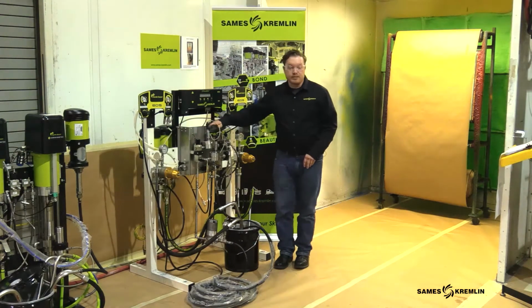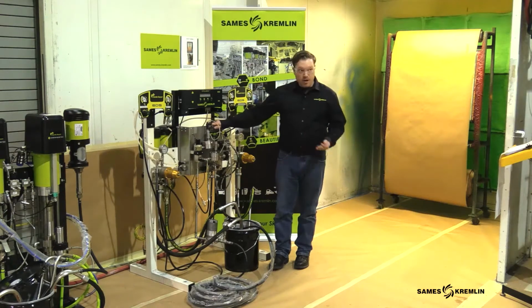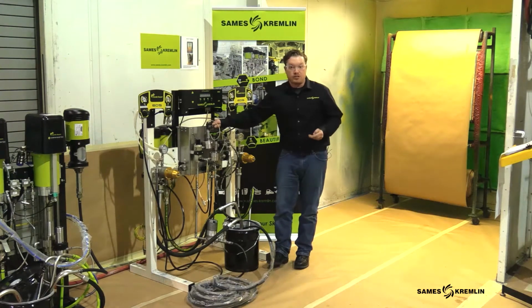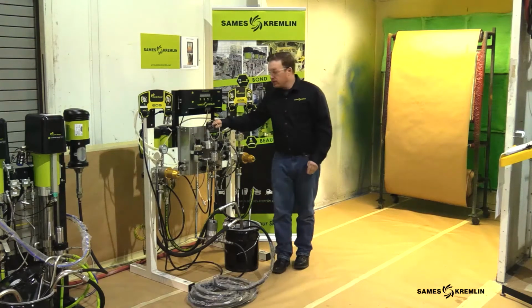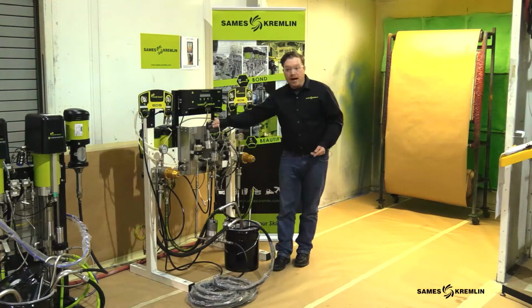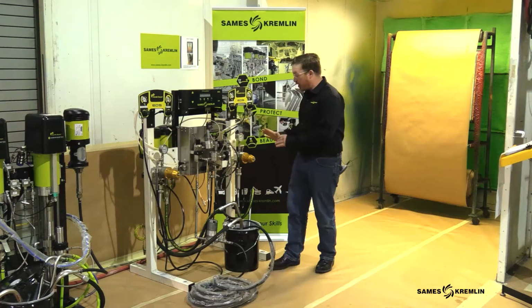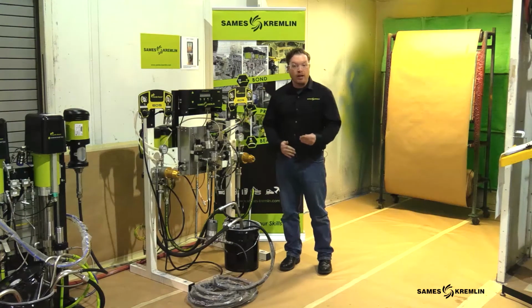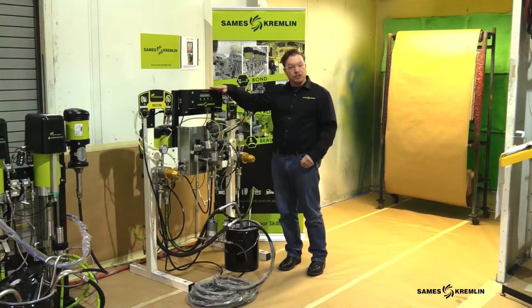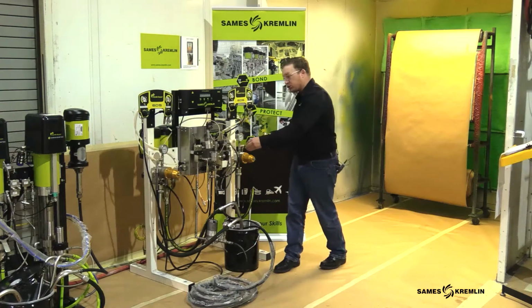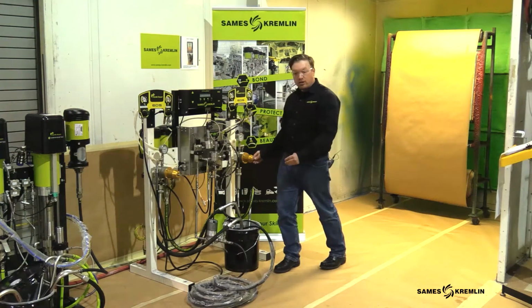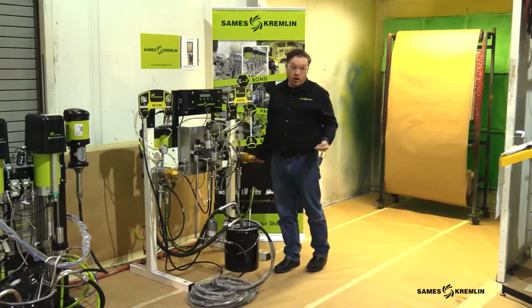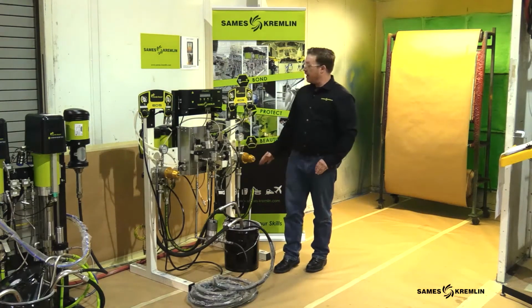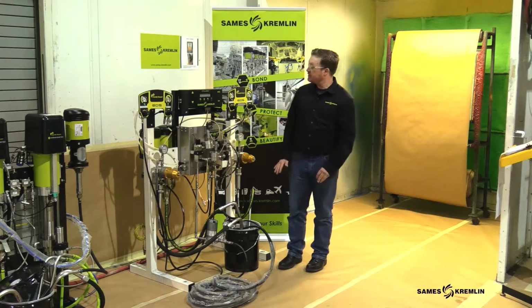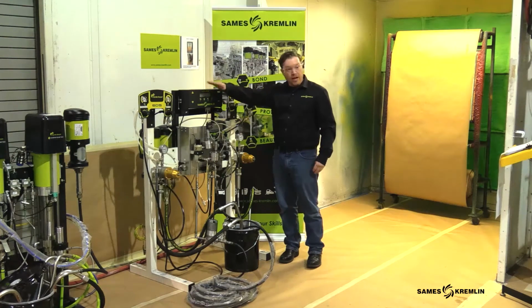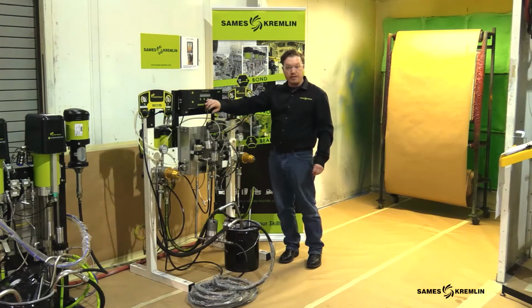That 10 to 15% value is a very rough value, and it's meant to be a great starting point for your installation. That's what I do based on my experience, 10 to 15% is a good starting point. And then once the system is up and running, you may see some ratio fluctuation here and there. As you bring those pressures in closer to the 10 to 15, maybe 20, depending on certain viscosities and differences in viscosities, you'll see that ratio will balance out and be more steady.